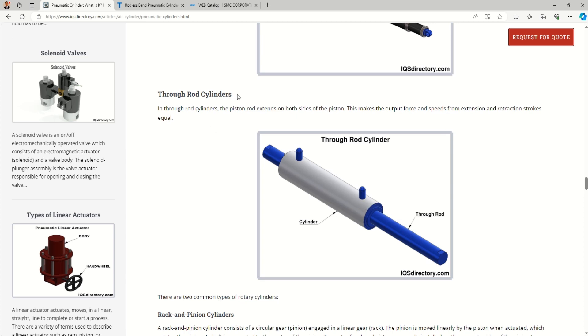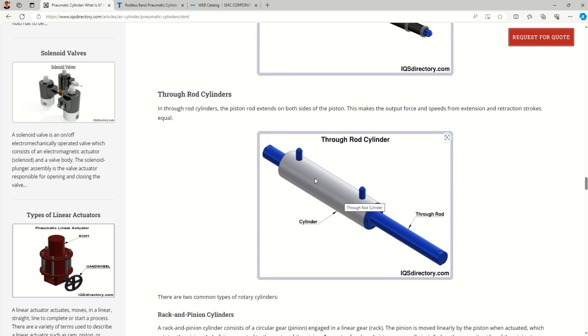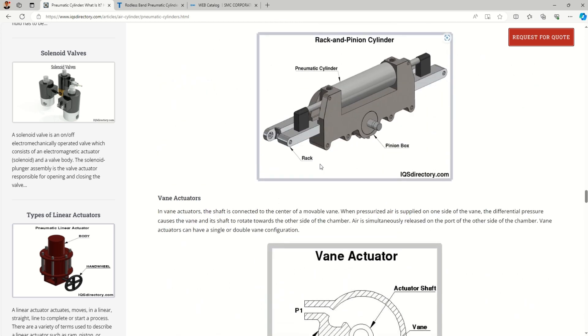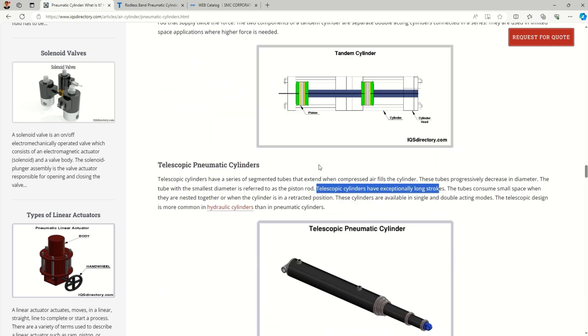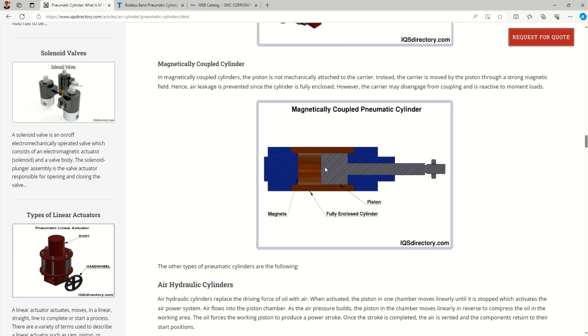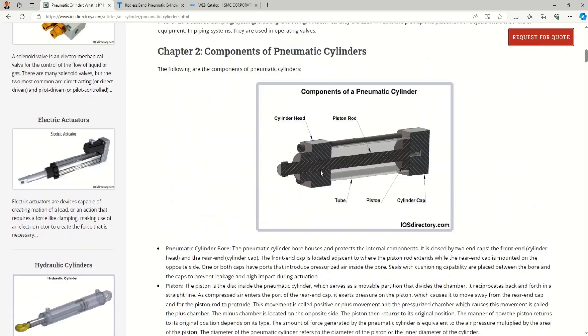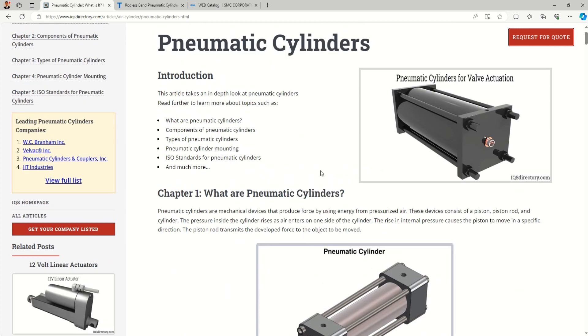Through-rod cylinders have the rod coming out from both sides of the cylinder. The advantage is that we get constant force in both directions since the rod area is the same on both sides. There are also other types depending on operating conditions, such as rack and pinion cylinders. These are the main types of actuators you should know — how they function, their uses, and their applications.